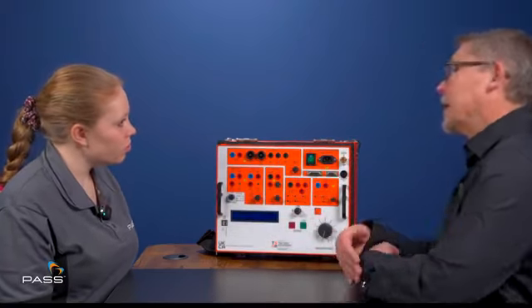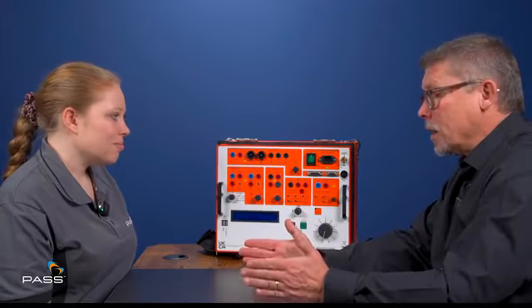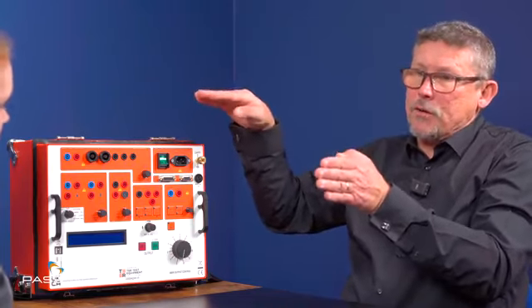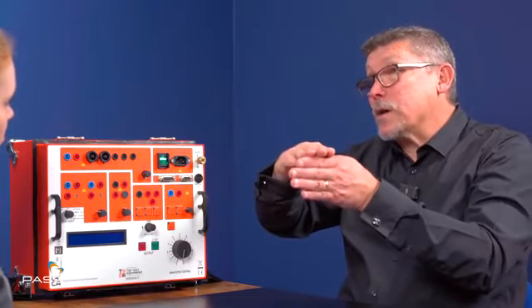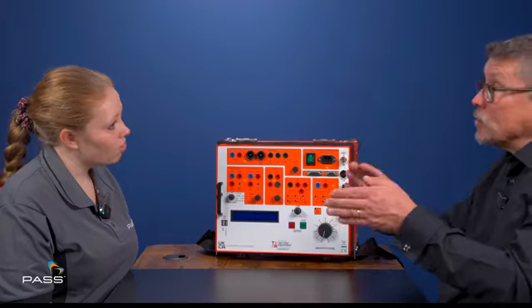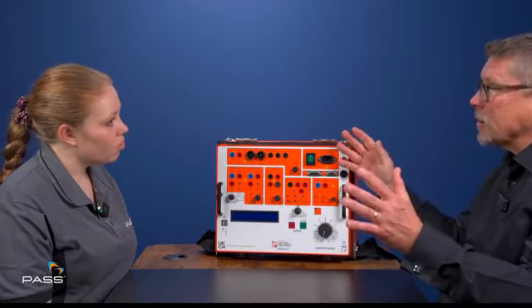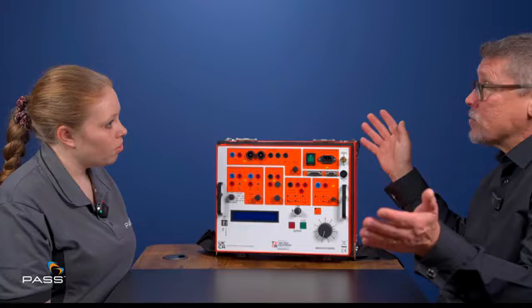But we saw an opportunity there because there are protection devices in the world called auto reclosers. They're designed so that when, for example, you've got an overhead line and you've got a tree near it, that tree through the summer grows. And let's say either one or 2 things happens. The tree grows and hits the cable, in which case it'll go buzz, buzz, burn, burn, break the tree bit off. And now there's not a problem again. So the auto recloser is designed that it'll auto reclose. And if it sees the incident has gone, it's minimal interruption to power.